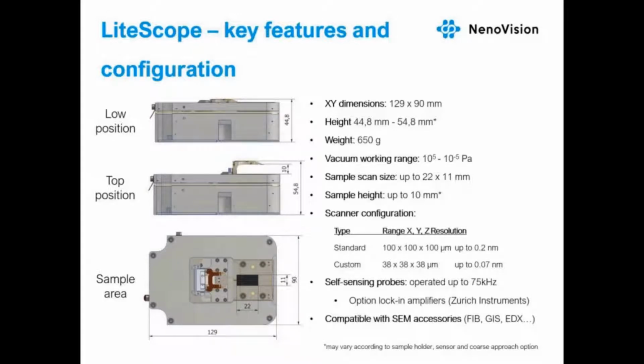The standard configuration offers big scan range, 100 by 100 by 100 microns, with resolutions up to 0.2 nanometers. The custom configuration has a reduced scan range to 38 by 38 by 38 microns, however, with increased resolution up to 70 picometers. Then we offer two different macro approach configurations and also LiteScope version for field-free and immersion SEMs. And since LiteScope can be tilted, it is compatible with standard SEM accessories such as focused ion beam, gas injection system, and so on.